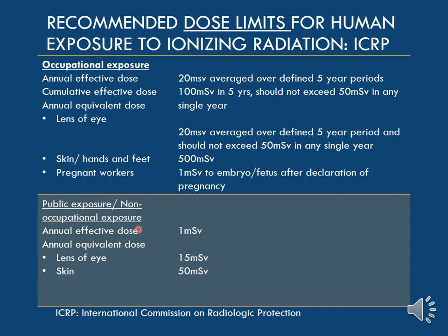For public or non-occupational exposure, the annual effective dose limit is just 1 millisievert, the annual equivalent dose to the lens of the eye is 15 millisieverts, and the skin limit is 50 millisieverts. The public is allowed less radiation because they should not normally be getting exposed to ionizing radiation beyond this. If the public exceeds this limit, it indicates something is wrong — too many radiographic examinations, or a radiation leak or natural disaster.